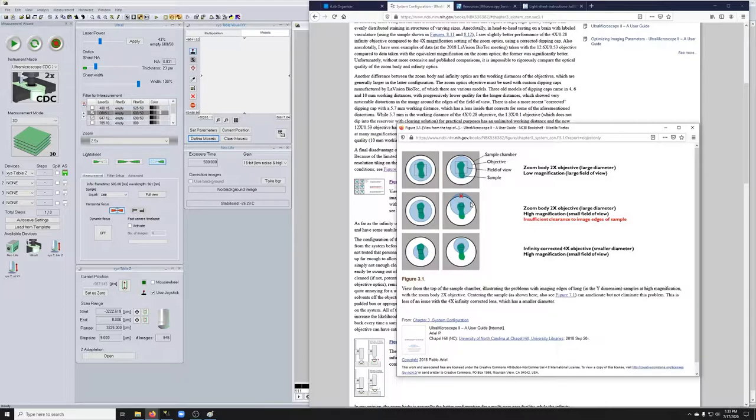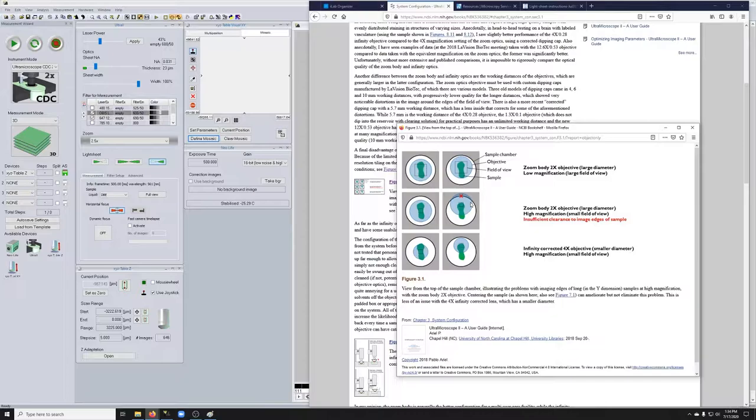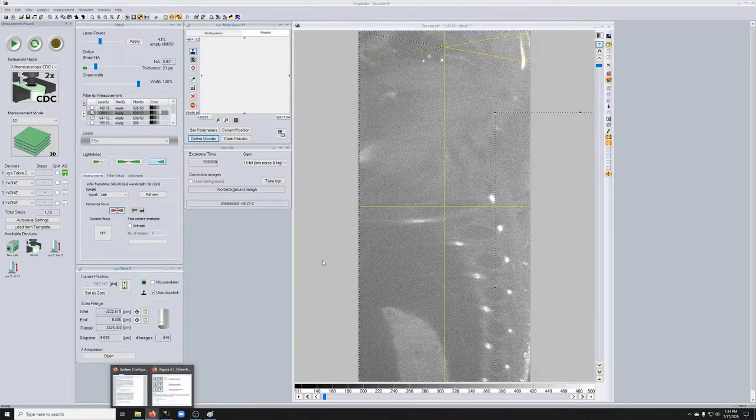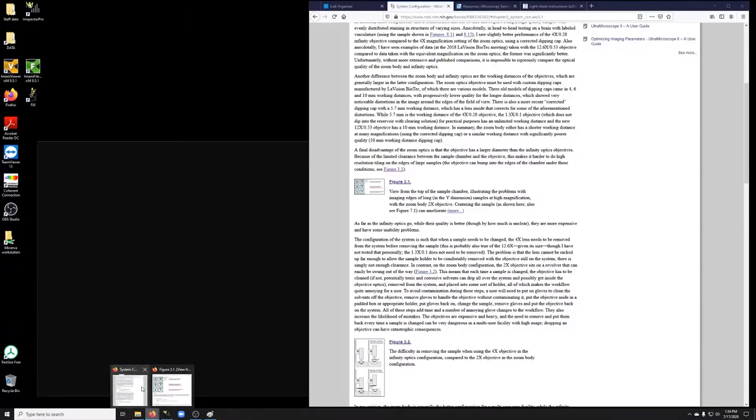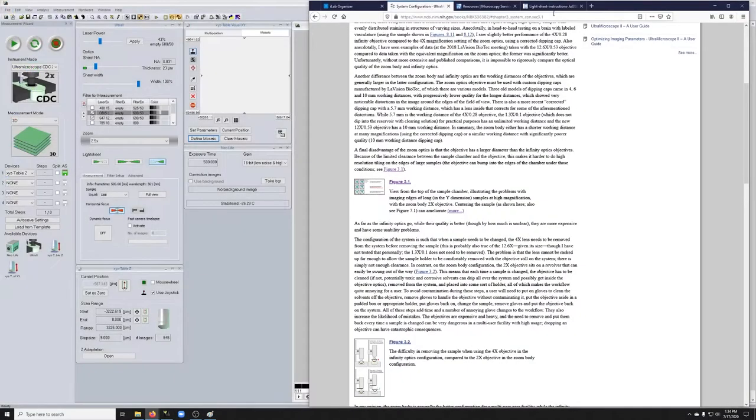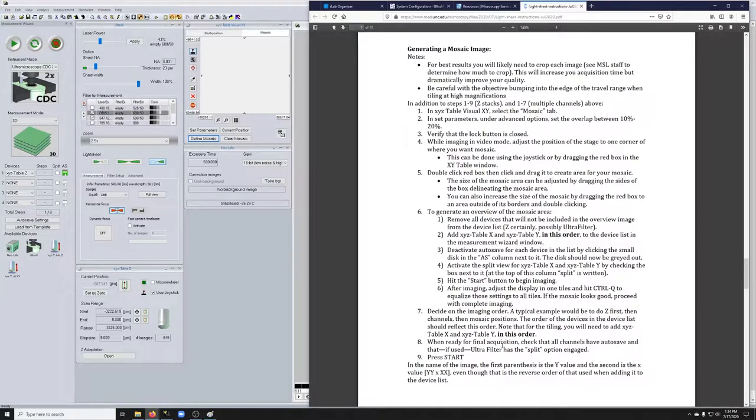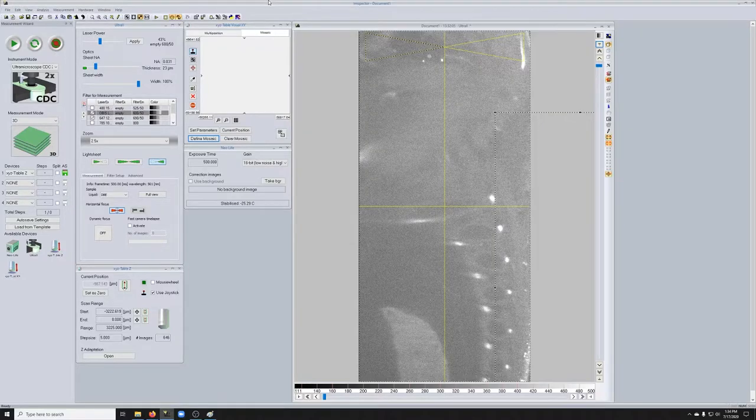All this to say, if you're at high mag and you have a big sample size, you may not be able to tile it completely, and you may end up bumping into things. So if you're in a situation like that, ask us for help. We can provide some assistance in figuring out how best to mount things to make this work. So that was the second recommendation over here. And so now we're just going to go through these steps. So I'm going to exit that, you can read through them at the same time as you're looking at this video.